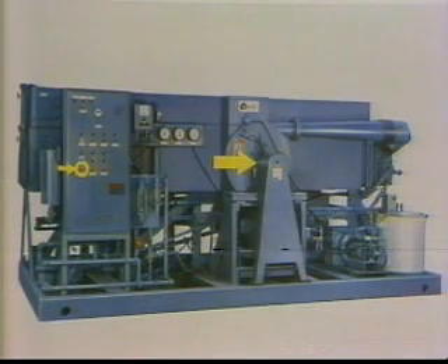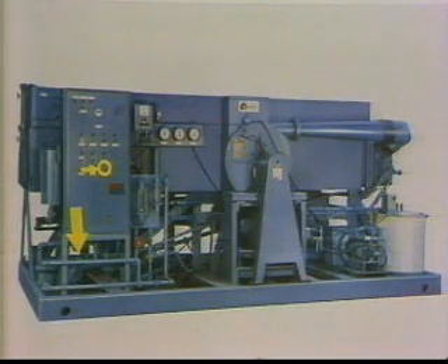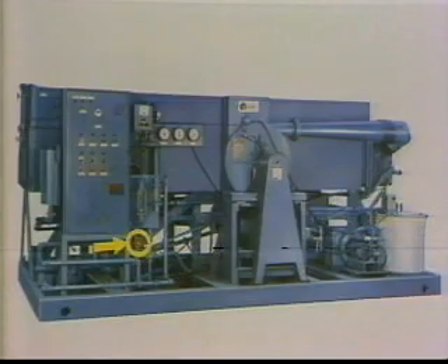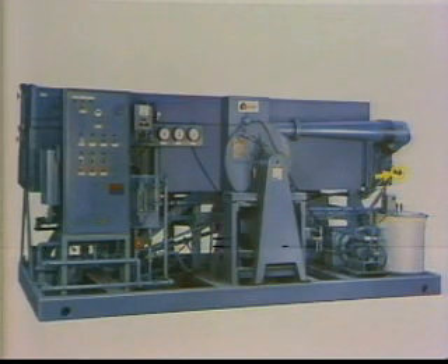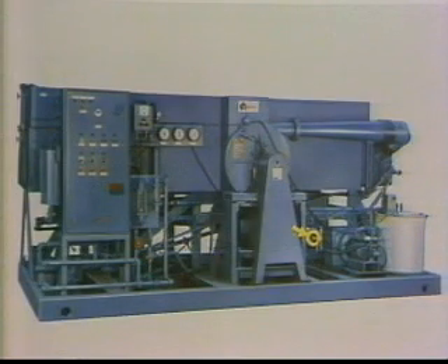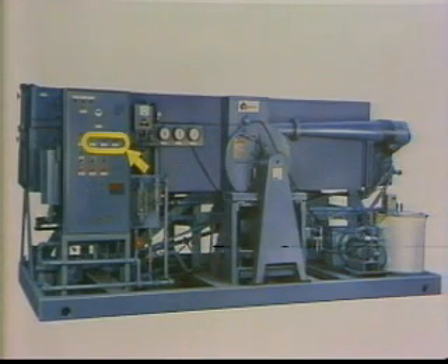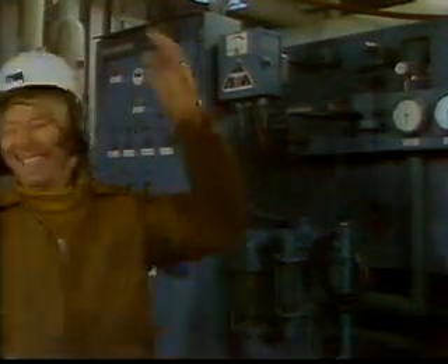Next, turn the centrifugal compressor off, the pump motors off, and close the feed water shutoff valve. Open the vent condenser valve and close the desuperheated water valve. Then, turn the heaters and lube oil pump off, and the unit is ready to be fired up for next time. Okay, I know that sounds like a lot to keep up with.